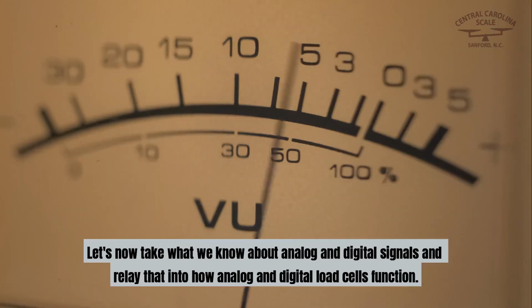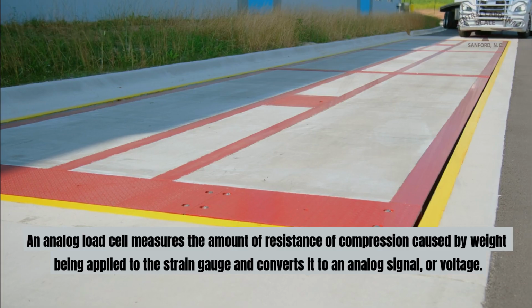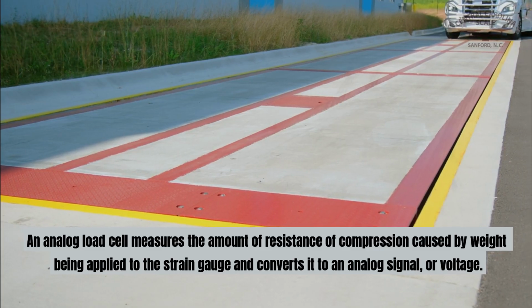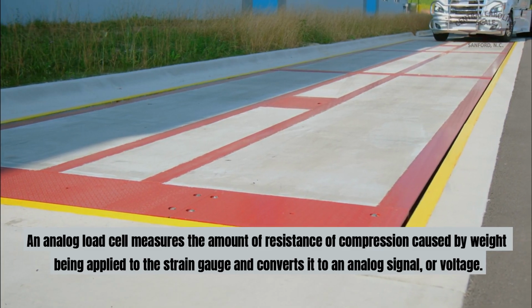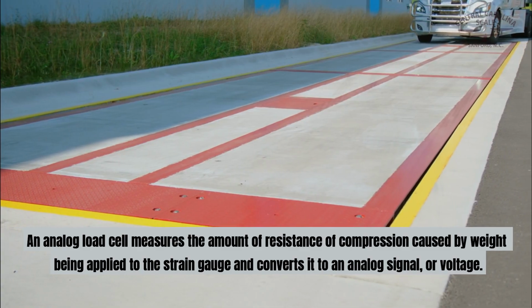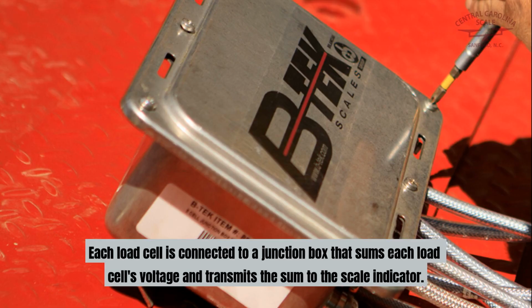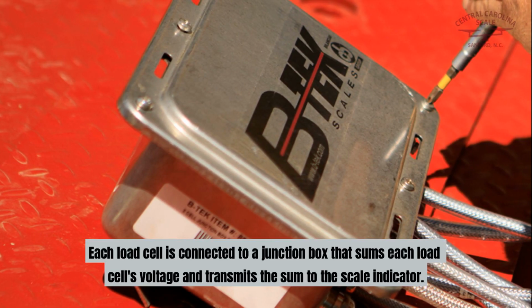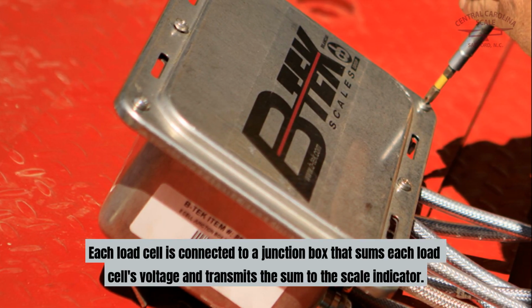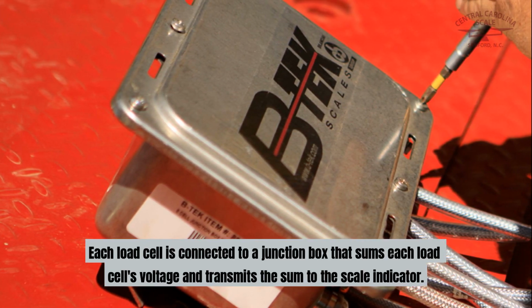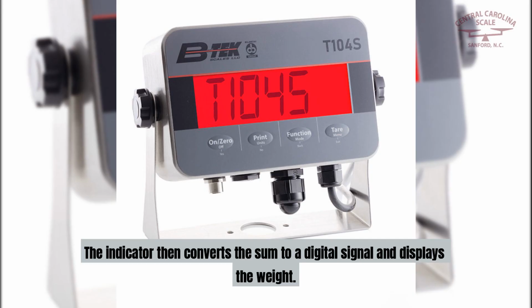Let's now take what we know about analog and digital signals and relay that into how analog and digital load cells function. An analog load cell measures the amount of resistance of compression caused by weight being applied to the strain gauge and converts it to an analog signal or voltage. Each load cell is connected to a junction box that sums each load cell's voltage and transmits the sum to the scale indicator. The indicator then converts the sum to a digital signal and displays the weight.